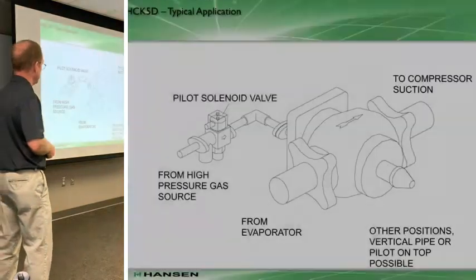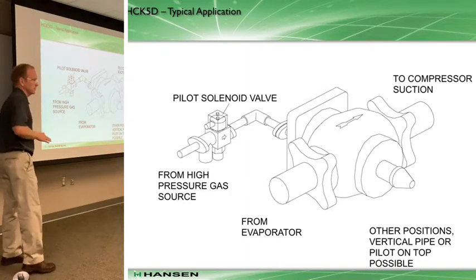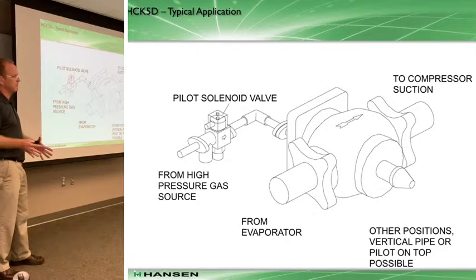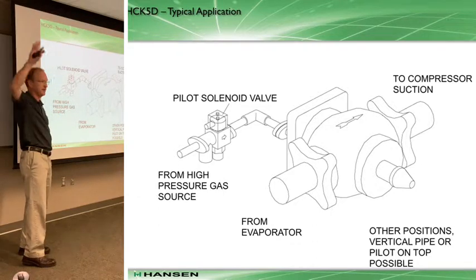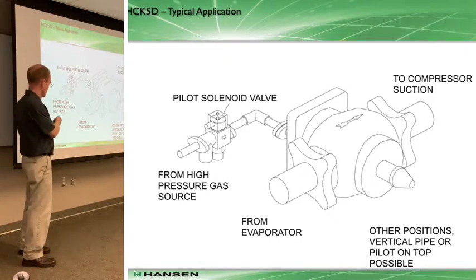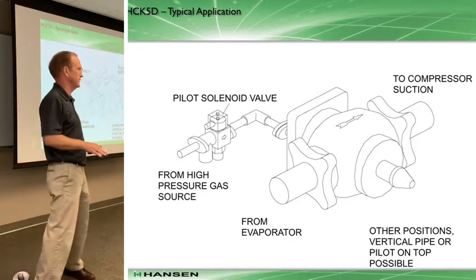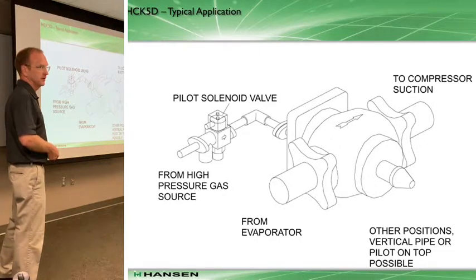The HCK5D is a drop-in replacement for the HCK2s - same flange pattern, so you can drop in and replace an HCK2 with an HCK5D, and it still only requires one pilot solenoid valve. Unlike the HCK5 where you have auxiliary piping to fit, with this there's no additional piping required. It's just one solenoid valve that activates a high pressure source on top of the HCK5D. I think it's a great conversion to consider - a safer valve that provides a lot of safety and protection.